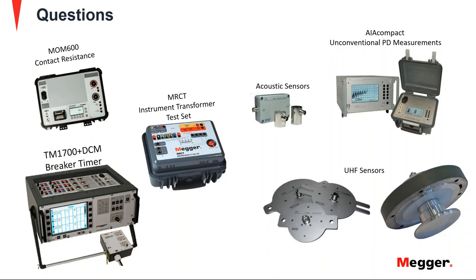And well, one of the benefits of using the DCM technology was using it for the application of GIS. So other breakers definitely can be tested, and there are some breaker applications that definitely require disconnecting them from ground, or they don't even have a way to disconnect, because there's a direct connection between equipment. So those situations are very good applications for the DCM, not only GIS.